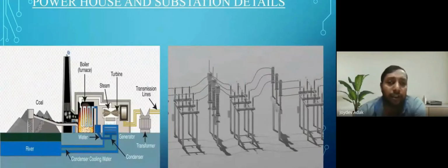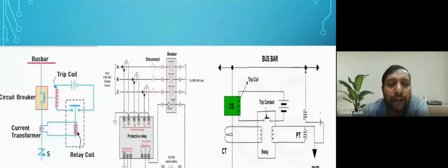Now, after that, we have to identify faults in the system. This is the basic relay system: after any fault occurs in the system, how will we detect it? This is the basic drawing. This is the bus bar, and this is supplying power to the consumer. The current transformer is placed here, the circuit breaker is placed here, and this is the basic relay circuit.